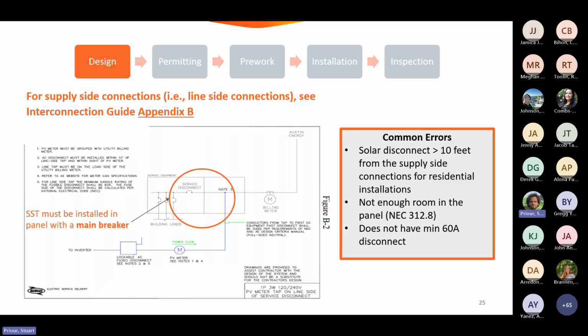So for supply side connections, or line side taps, as they're colloquially called sometimes, you can look at the interconnection guide appendix B. If you're doing a supply side tap, you will need to have it done in a main panel that's got a main breaker. So if there isn't a main breaker, you'll need to upgrade that main panel so that you can do a supply side tap. Some common errors are that the solar disconnect isn't within 10 feet of the tap, which is a local requirement and an NEC requirement.